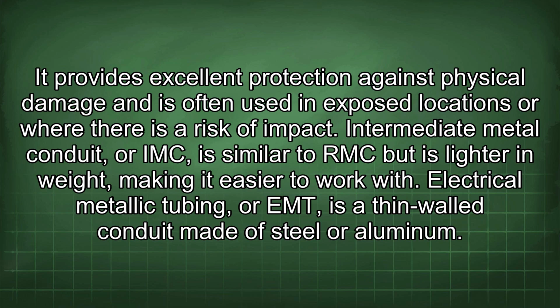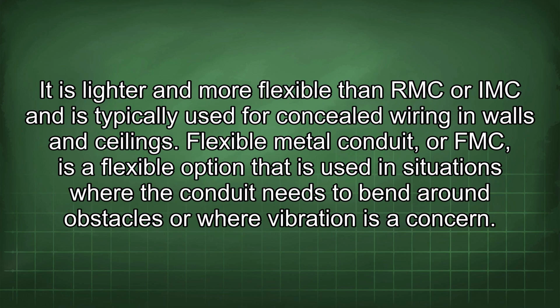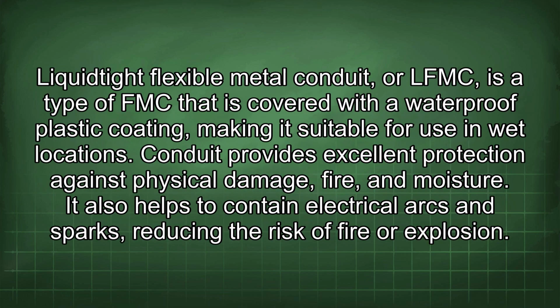Intermediate metal conduit, or IMC, is similar to RMC but is lighter in weight, making it easier to work with. Electrical metallic tubing, or EMT, is a thin-walled conduit made of steel or aluminum. It is lighter and more flexible than RMC or IMC and is typically used for concealed wiring in walls and ceilings. Flexible metal conduit, or FMC, is used in situations where the conduit needs to bend around obstacles or where vibration is a concern. Liquid-tight flexible metal conduit, or LFMC, is a type of FMC covered with a waterproof plastic coating, making it suitable for use in wet locations.